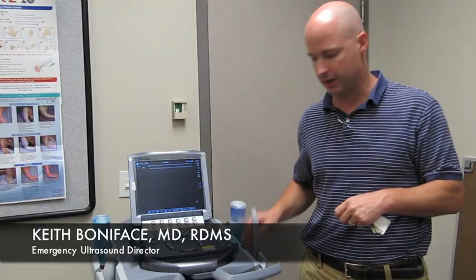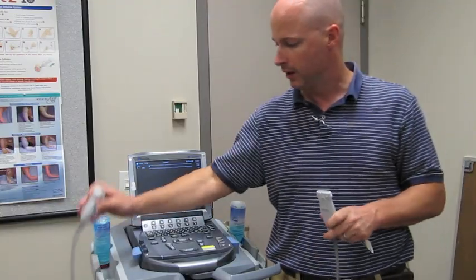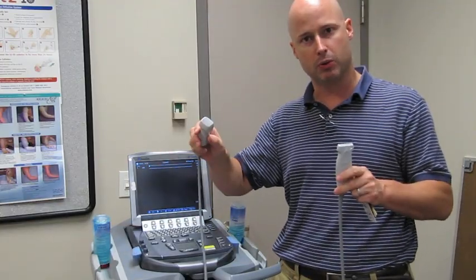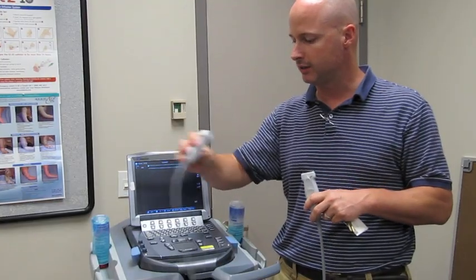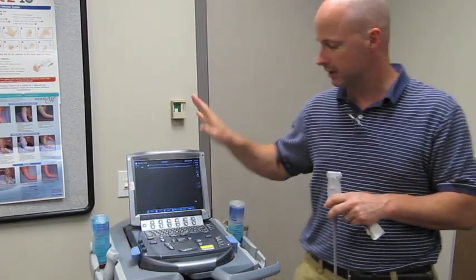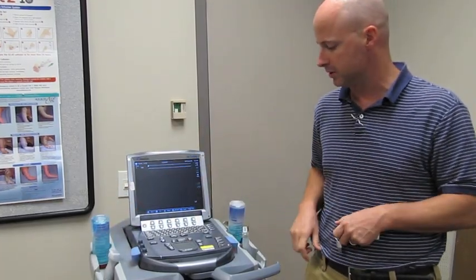We have a selection of 2 probes on this machine. At Prince George's we have 3 probes on the machine. And once you decide which probe you want to use, you can set up the machine to send the image from that probe to the processors.